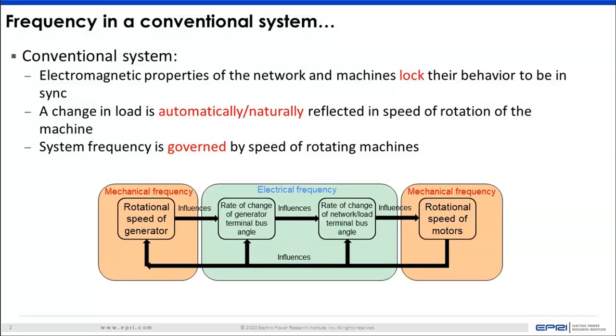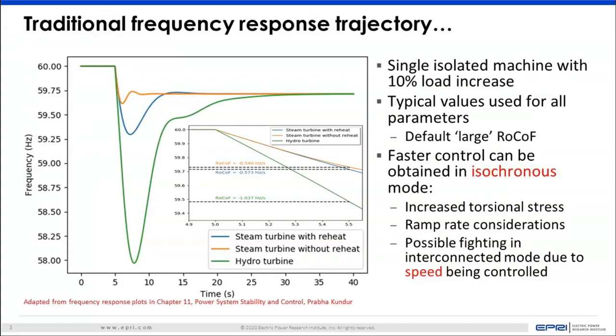Now, as you see on the diagram below, what essentially happens is that when you have the change in the rotational speed of motors, which are a majority of the load, inherently it influences both electrical frequency and mechanical frequency on the generation side. And then your system frequency is governed by the speed of these rotating machines, hence the term governor that we all know.